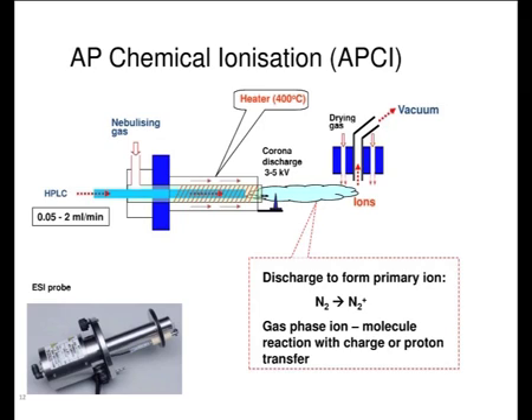This is where the ionization takes place. Nitrogen gets ionized, and when it strikes your molecules, the charge gets transferred and the compound gets ionized. This is the process of chemical ionization. Then finally, the compounds which are ionized enter the vacuum in the mass spectrometer. Generally, this technique is used for the analysis of mid-polar compounds or compounds which are very difficult to ionize. The main difference from ESI is that in ESI the compound ionization takes place in liquid form, and in the case of APCI, the compound gets ionized in the gaseous form.